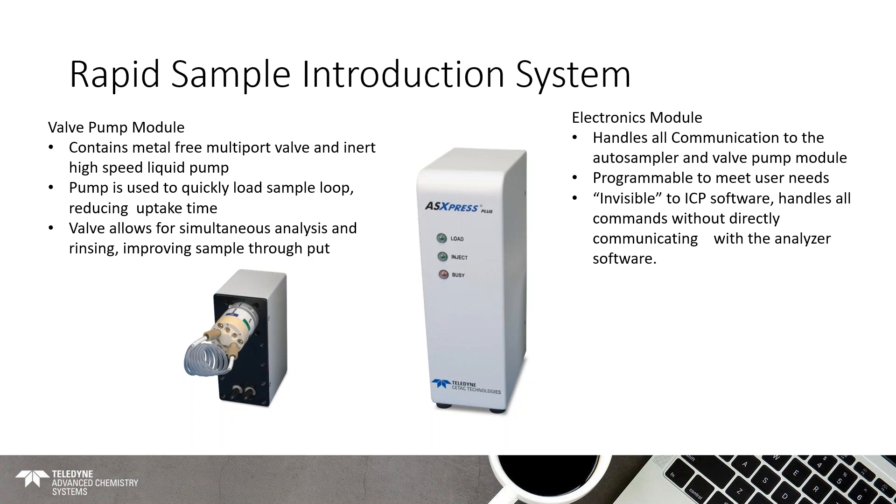So, this valve separates essentially the nebulizer from the autosampler, which allows for both simultaneous analysis and rinsing of the sample probe, which improves your sample throughput because then you don't have to wait to rinse out the system between each. And it improves your uptake time because rather than having your peristaltic pump drive your sample or pull your sample from the tip of the probe all the way through to the nebulizer, what we're using is this fast pump to very quickly pull the sample close to the nebulizer. And then we still use the onboard peristaltic pump for the ICP to introduce the sample. So, that's still controlled by your ICP software. And so, your sample introduction remains the same. On the right, we have the electronics module. And what this is, kind of the brains of the operation. It handles all communication between the computer and the autosampler, and the valve pump module gets everything in sync.